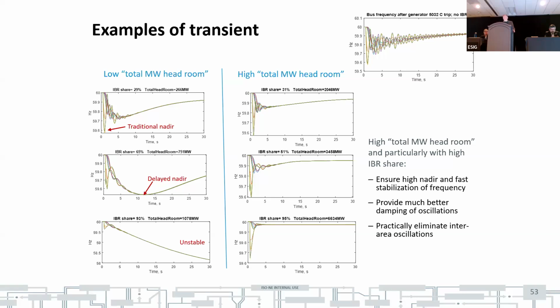And that slide shows samples of what type of transient could be expected. On the top right corner, you see the transient when there is no inverter. So you see a lot of oscillation with different frequencies and damping, whatever was expected from eigenvalue analysis. On the left side column, it shows transient for different penetration of IBR and relatively small cumulative headroom for control. The top figure shows a traditional nadir, which is happening within 3 to 5 seconds. The middle plot shows a delayed nadir, which you typically don't see in a traditional power system. And the bottom picture shows instability, when frequency is drifting gradually to an unacceptable level.